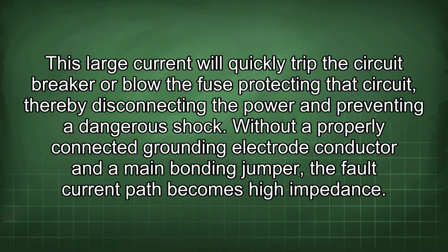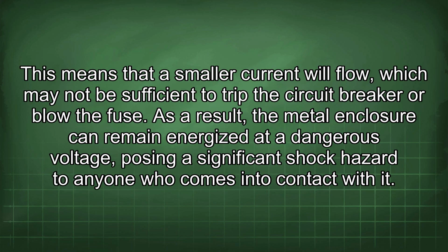Without a properly connected grounding electrode conductor and a main bonding jumper, the fault current path becomes high impedance. This means that a smaller current will flow, which may not be sufficient to trip the circuit breaker or blow the fuse. As a result, the metal enclosure can remain energized at a dangerous voltage, posing a significant shock hazard to anyone who comes into contact with it.